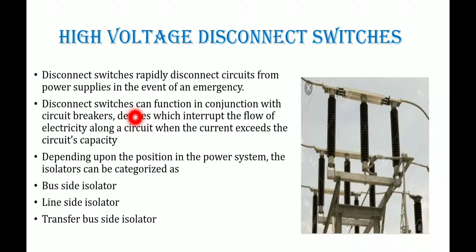Whatever we do, the circuit breaker is used for tripping the circuit, opening and closing contacts, but the open contacts of the breaker cannot be seen physically from outside. Since it's not visible to us, it is recommended not to touch an electrical circuit just by switching off the circuit breaker, because we can't physically know whether the contacts are open or closed.